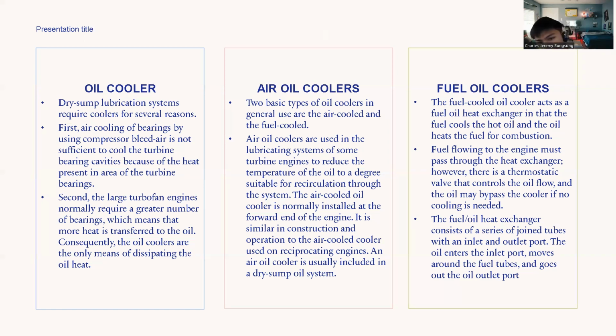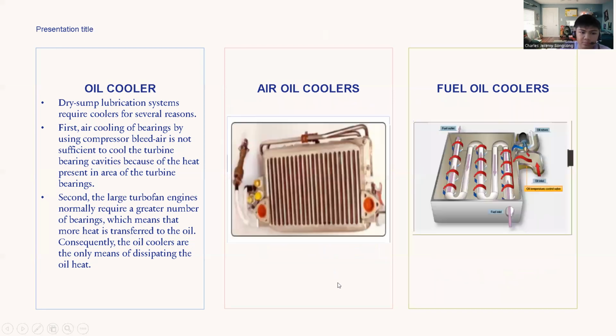while the fuel oil cooler acts as a fuel oil heat exchanger in that the fuel cools the hot oil and the oil heats the fuel for combustion. Fuel flowing to the engine must pass through the heat exchanger. However, there is a thermostatic valve that controls the oil flow, and oil may bypass the cooler if no cooling is needed. The fuel oil heat exchanger consists of a series of joined tubes with an inlet and outlet port. The oil enters the inlet port, moves around the fuel tubes, and goes out the oil outlet port.